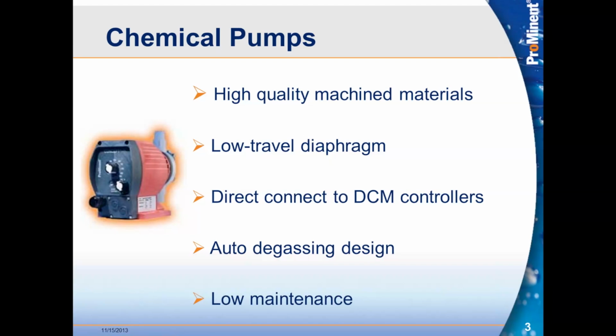What that means is when there's a feed event being directed out of that pump room, it takes a long time for that chemical to get through all the piping and out to the pool. Then it takes a while for that to mix in the pool, and then it takes a long time for us to get water back to the mechanical room and have the controller sense that there's been a change in the chemicals based on the feed event. So there's a lag time between when the feed event starts and when we realize that there are changes happening in the water, and the controller can respond to that. That lag time in the past had caused a lot of overfeed events. With the PID now, we can more precisely modulate that feed event, and we've almost eliminated any overfeed situations off of that pool. So it's been a huge tool for this operator to use the PID loop and our pumps connected to our controllers.